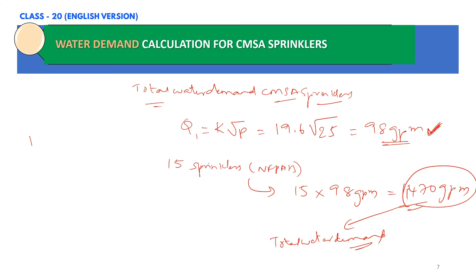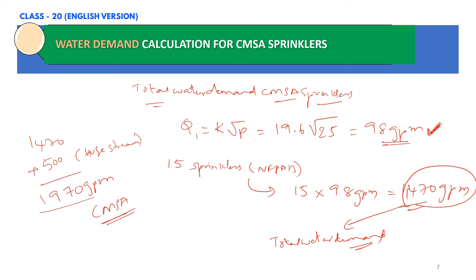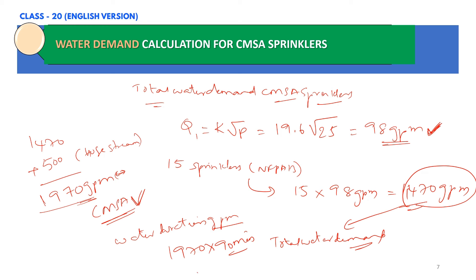We now add the sprinkler demand of 1,470 GPM to the hose stream allowance of 500 GPM, giving a total water demand of approximately 1,970 GPM for this storage warehouse with CMSA sprinklers. The water tank capacity is then calculated as 1,970 GPM multiplied by the 90-minute duration, resulting in approximately 177,300 gallons. The water tank capacity shall be a minimum of 177,300 gallons, and the pump selection will be based on this total water demand.